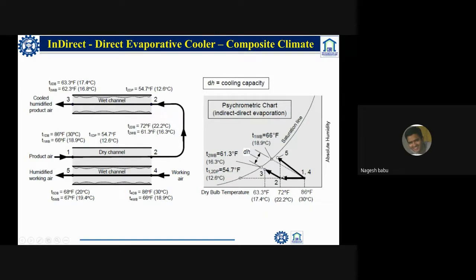But if we want to further reduce the temperature, then we can go for something more. On a typical day, having an inlet temperature of around 30 degrees centigrade, from an indirect evaporative cooler we can get around 22.2 degrees centigrade. And if we want to further reduce the temperature, say up to 17 degrees centigrade, then we can also integrate another wet channel, that is, another evaporative cooling medium, so that we can further reduce the temperature. So with this, we are almost meeting the saturation line, that is, the 100% humidity line. Here we are almost going towards very cold conditions, up to 17.4 degrees centigrade.